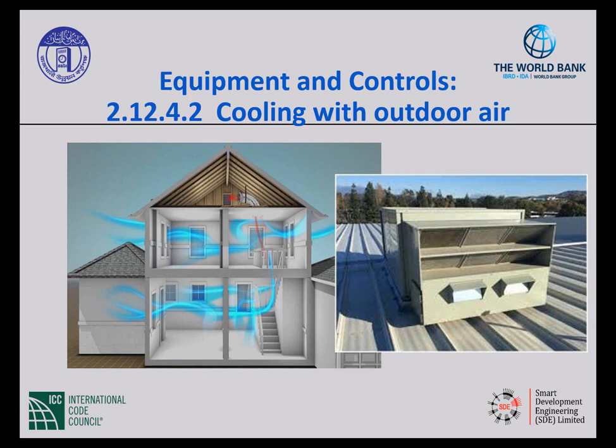You don't want to use that air, so that would be an exception. Where the need for humidification or dehumidification requires the use of more energy than is conserved by using the outside air. So if I bring in all that outside air and it has too much moisture in it, and it's going to cost me way more to dehumidify than it would to just run the air conditioner, then I don't have to do that. Or where the use of outdoor air cooling would affect the operation of other systems, so as to increase the overall energy consumption of the building. Would it make other systems run harder or something? So we'll talk more about economizers in a few minutes.